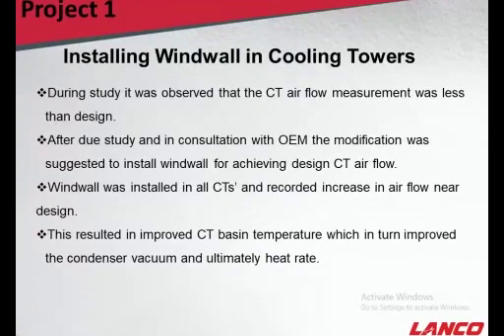The problem was that due to the cross flow, the air was bypassing and short circuiting in the cooling towers. That's why the actual flow was not coming to the design value, and that was ultimately affecting the basin temperature, and in turn it was converted into lesser vacuum in the summer, particularly the summer season.